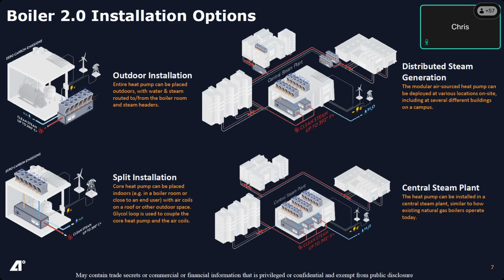We do have some ambitions by 2029. We're going to have a larger unit, about 4.5 megawatts, and then central plants built around our technology make a little more sense. But having said that, when you stack a lot of smaller heat pumps, you actually get a lot more turn down capability than you would by putting in a few larger heat pumps. So it depends on what the steam profiles of facilities look like to see if that's something you want to pursue. You can jump to the next slide.